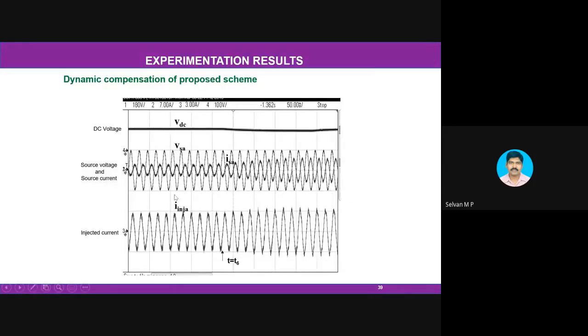Here you can see that there is an increase in source current. The increase in source current indicates an increase in real power generation. It is always 180 degrees out of phase with the voltage. If the current flows into the machine, then it will be in phase. Since current is flowing from the machine to the grid, it is completely out of phase. This 180 degree phase difference indicates that only real power flows. Here the magnitude of the current is very small. As time increases, it is increasing. That indicates that wind speed has increased, so real power output has also increased. During that time, it needs more reactive power. That reactive power is supplied by the STATCOM, which is evident from the increase in the magnitude of the injected current.